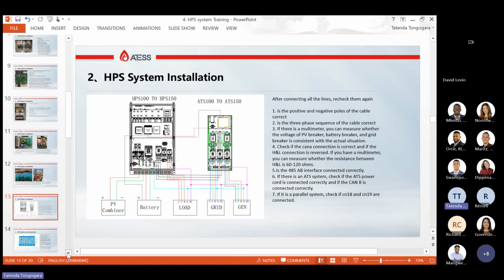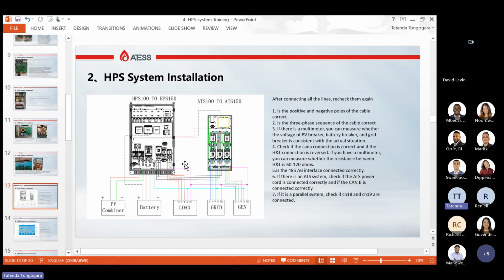The problem with wrong phase rotation is that it can lead to damage of the SCRs, which are found here. They're used for switching purposes. Sometimes ESCOM guys come and work on the line, they swap the phases, and you are not on site, and then the system will show a sequence fault. The best thing you can do is contact your client, they switch off the AC input breaker before it can damage anything, and then you can correct the phase sequence.